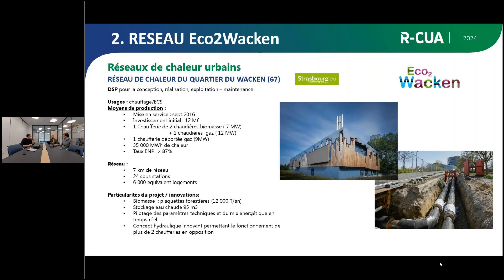On a également installé un ballon de stockage d'eau chaude de 100 000 litres. À l'heure actuelle, le réseau de chaleur en lui-même contient quasiment 7 fois plus d'eau que ce ballon, donc le premier stockage d'un réseau de chaleur, c'est le réseau lui-même. Pour la pose, on voit les deux tubes dans une tranchée — du diamètre 500 par tube — qui nécessitent des tranchées de 2 mètres de large dans des zones urbaines très denses en plein centre de Strasbourg, ce qui est très complexe en termes de gestion de flux routiers, de commerçants et de riverains.